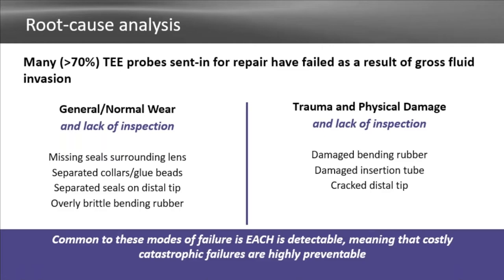So general normal wear and tear. We want to look for missing seals around the lens. We talked about the collars and the glue beads, the seals on the distal tip, and the overly brittle bending rubber. But we also want to look at damaged bending rubber, damaged insertion tube, and cracked distal tip.